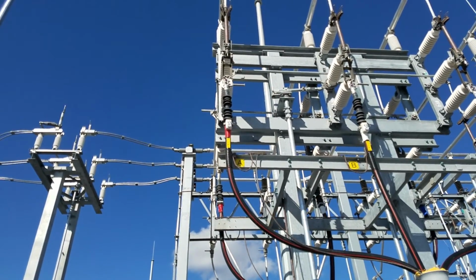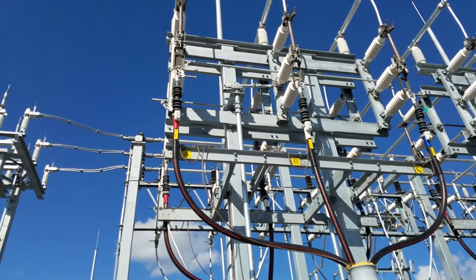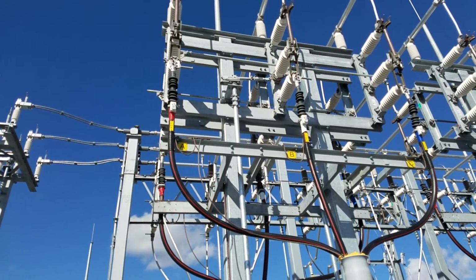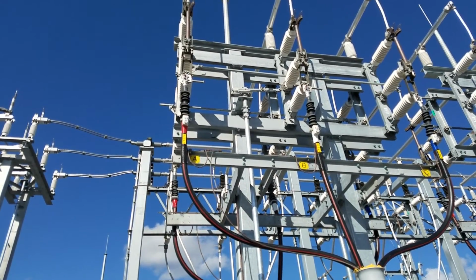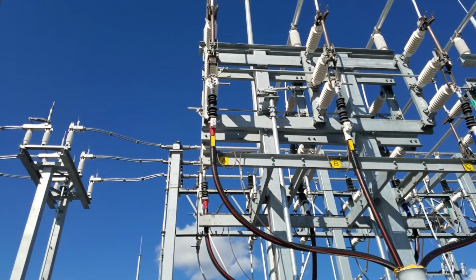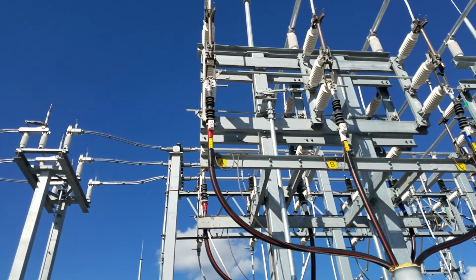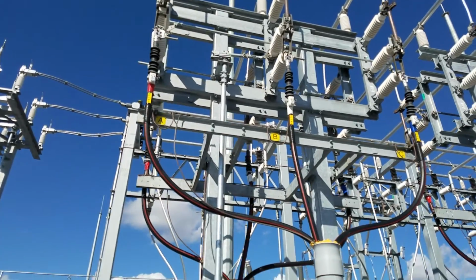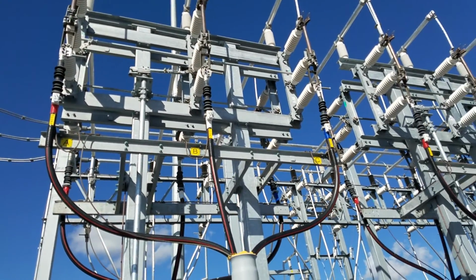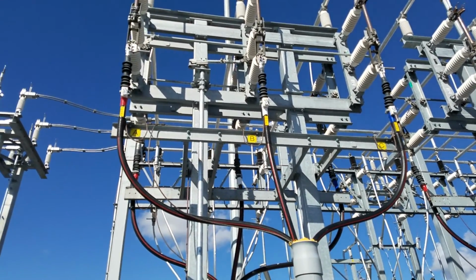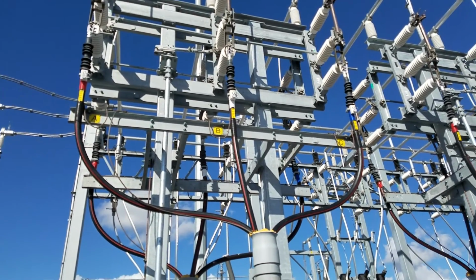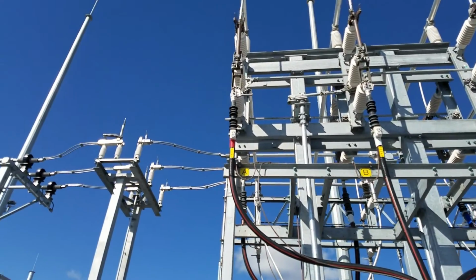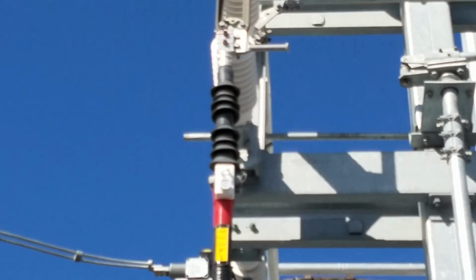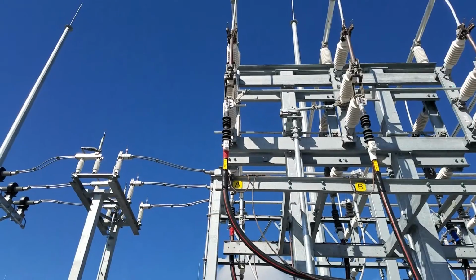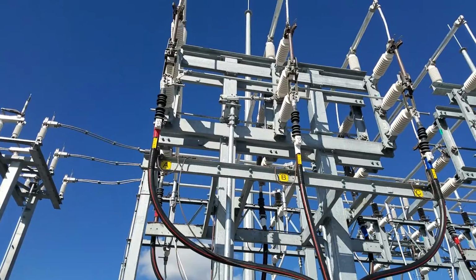The white things on there are called fault indicators. If there is a fault or a short of some kind, the device on the cable will turn red. So if you have a trip, you can come out here and you can see if it's on the red, white, or blue, and that'll tell you if it's basically A, B, or C phase, and you can go follow it out to the field from there. And there's multiple ones of these throughout the transformers. So it just makes it easier to locate your faults.